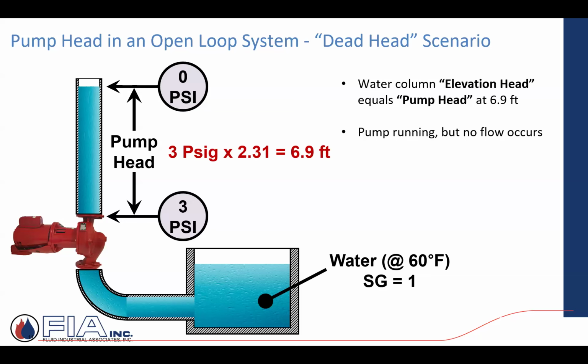So there's no flow. I'm just maxing out my differential, which in this case is 6.9 feet, which happens to be just the height of this open pump, or this open piping, I should say. Pump running, no flow occurs.